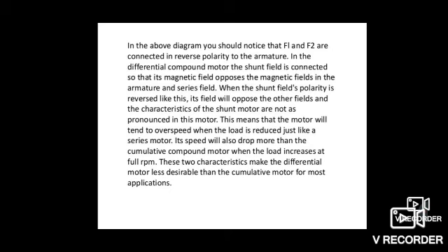This means that the motor will tend to overspeed when the load is reduced, just like a series motor. Its speed will also drop more than the cumulative compound motor when the load increases at full RPM. These two characteristics make the differential motor less desirable than the cumulative motor for most applications.